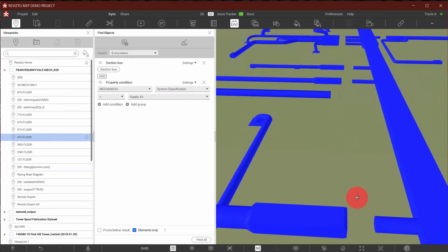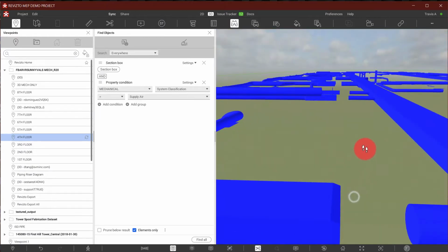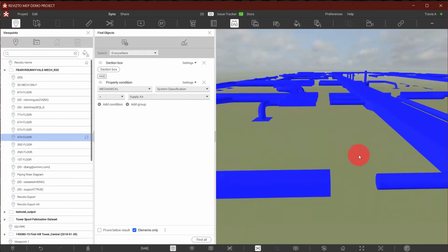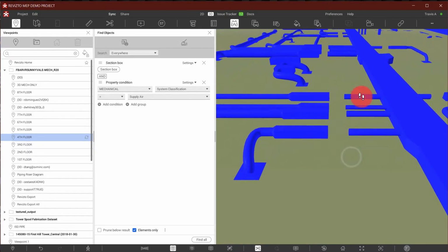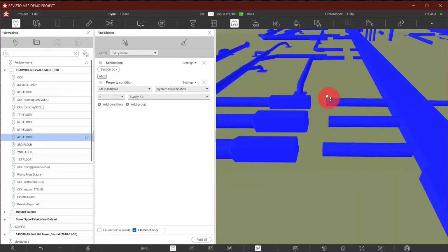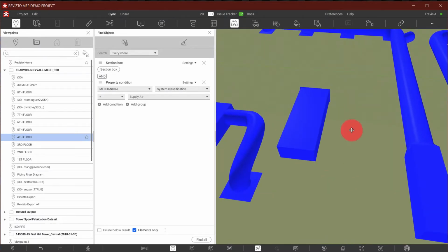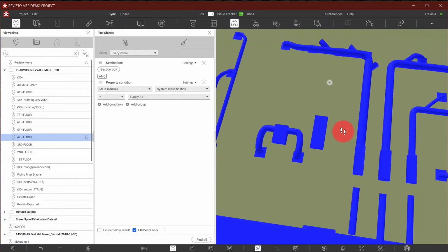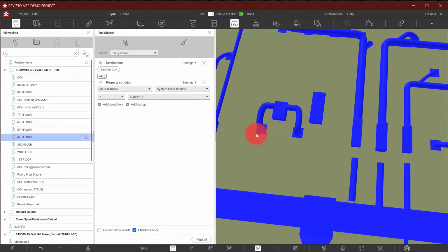Where this comes in handy is checking real quick. I can check where my VAVs are going. I can check different connections to equipment, the lay of the land. I can obviously look at this real quick and see we've got some return air coming up here into an open plenum spilling over there.